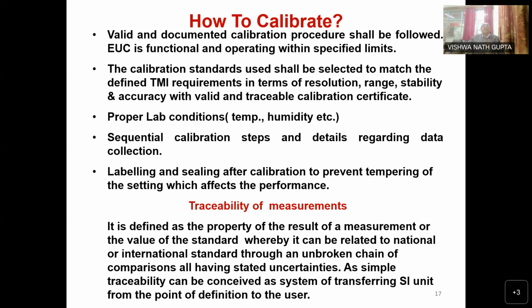This is the practical example I am giving, sir. We brought other equipment, but every time the slight variation continued. But the result of the winding resistance of the generator was giving okay what was desired. Later on, we checked the calibration certificate of the instrument we were using, and it had a slight variation. If we had incorporated that during measurement, it could have given us the correct result at that time. What I mean to say, sir, is what I have told earlier about industries: this is BHEL, whether this type of solution is there, just refer to your calibration laboratory and then incorporate the result.